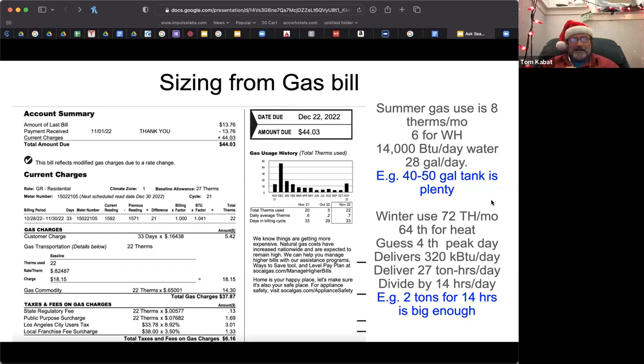Then looking at January, Greg mentioned that's when his daughter visits and she likes to run the temperature hotter. They used 72 therms that month, and I'd guess 64 of those therms were for space heating, with the other 8 for regular water heating and everything else. With 64 therms in a month, I'm guessing their peak day is about 4 therms of gas use. Putting that through their furnace at 80% efficiency would deliver 320 kilo-BTUs per day, the same as 27 ton-hours of energy in HVAC speak, where a ton is 12,000 BTUs. Dividing that energy by about 14 hours tells me a 2-ton heat pump could deliver 28 ton-hours in that peak day, taking only 14 hours to do it.